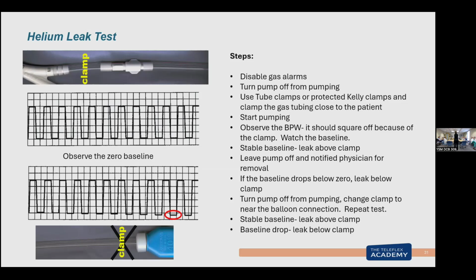The pump doesn't alarm unless there's a reason to alarm. It says, I see a problem. You don't see blood, but I see the problem. And so that's when I do the internal leak test.